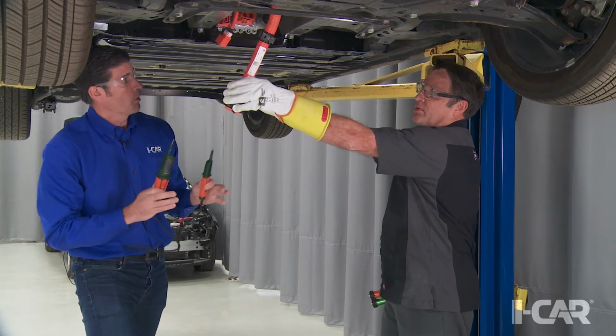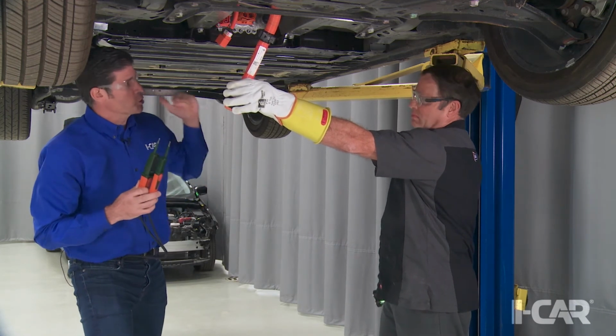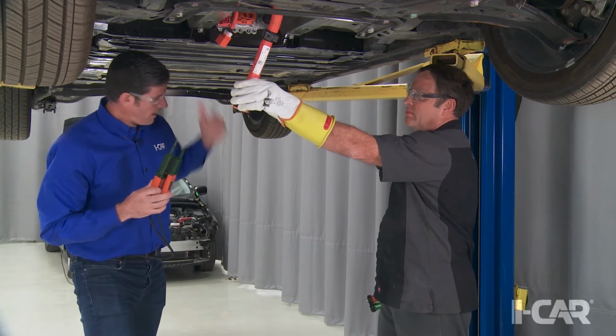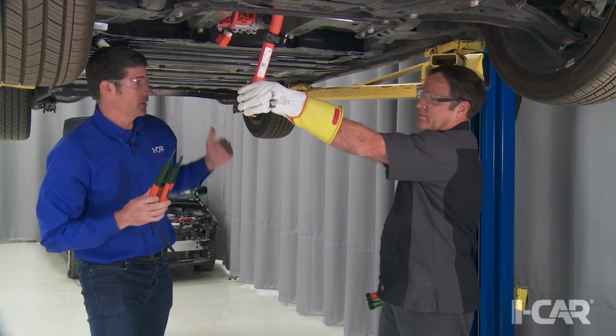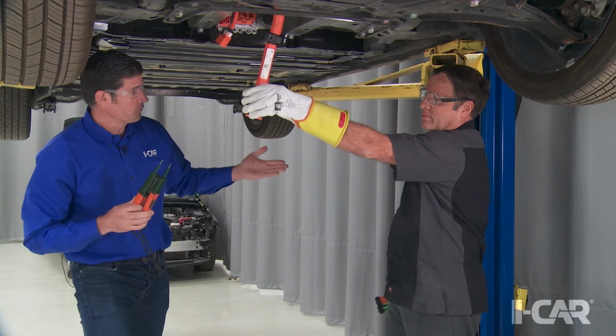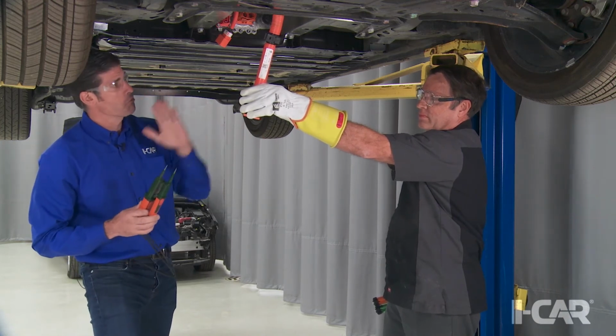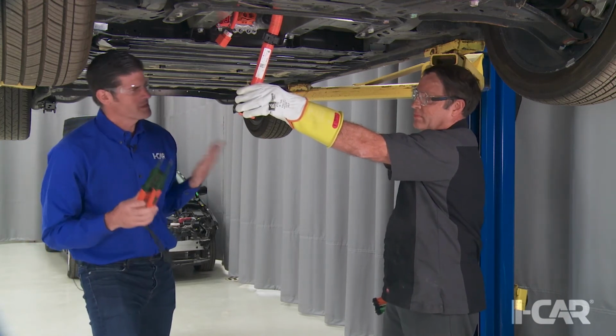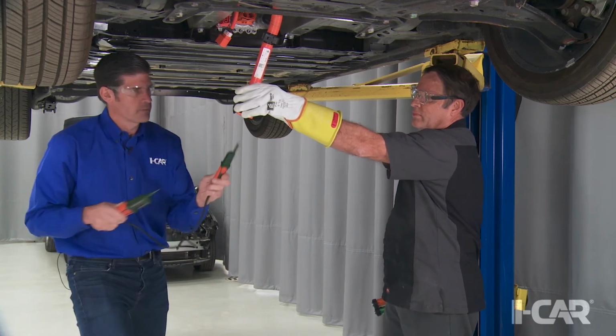So you're checking for any potential faults. When we talk about a certified disconnecting procedure, what a lot of European manufacturers follow is making you take 3 measurements. That's the reason I'm on the safety side, I like to make 3 measurements.